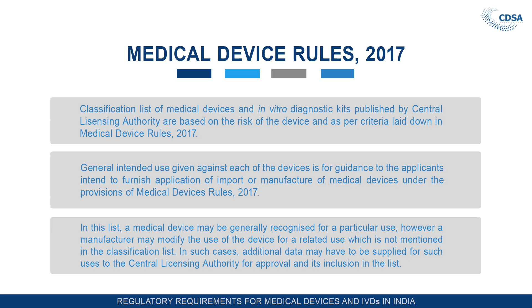In this list, devices may be generally recognized for a particular use. However, the manufacturer may modify the use of the devices for a related use which is not mentioned in the classification list. In such cases, additional data may have to be submitted to the central licensing authority for consideration and approval, and once it is approved by the central licensing authority, it is included in the said classification list.